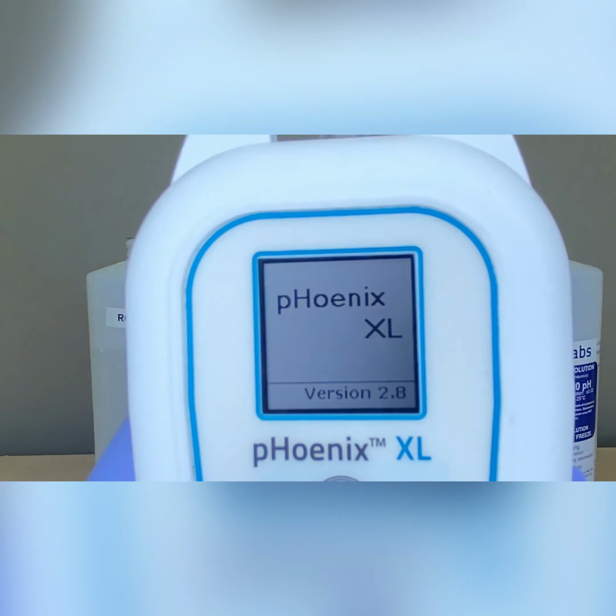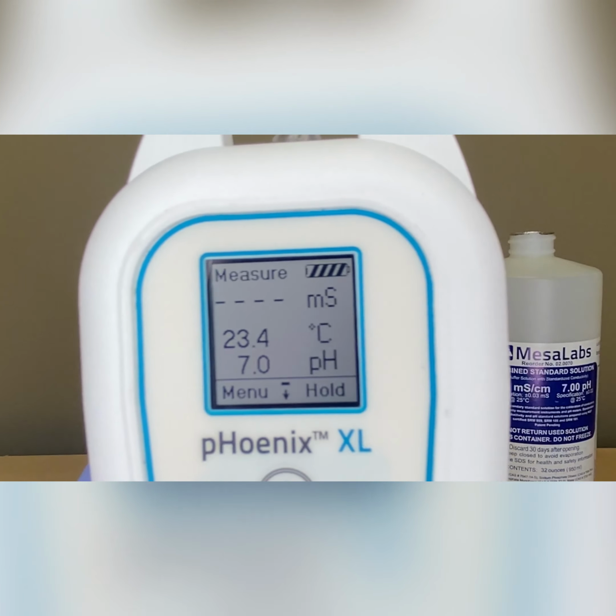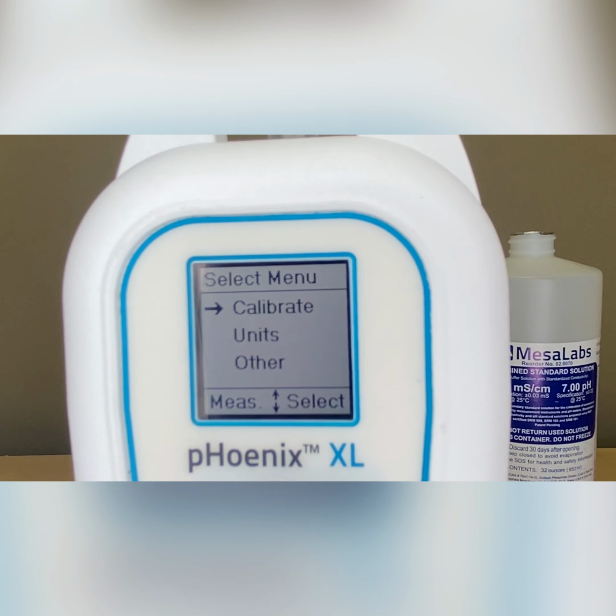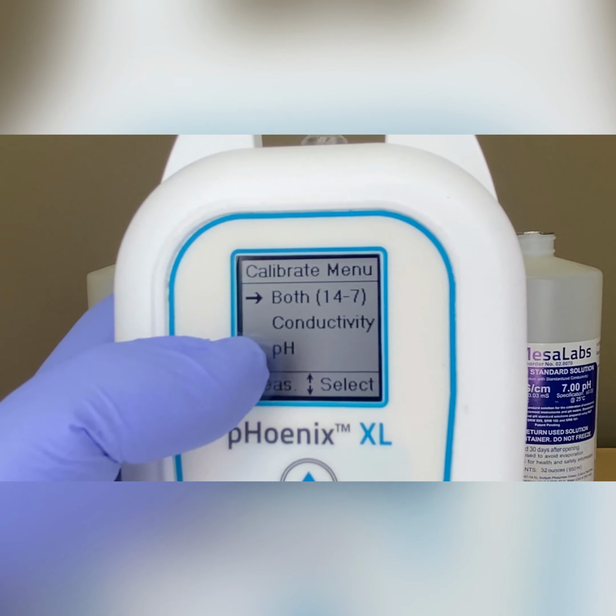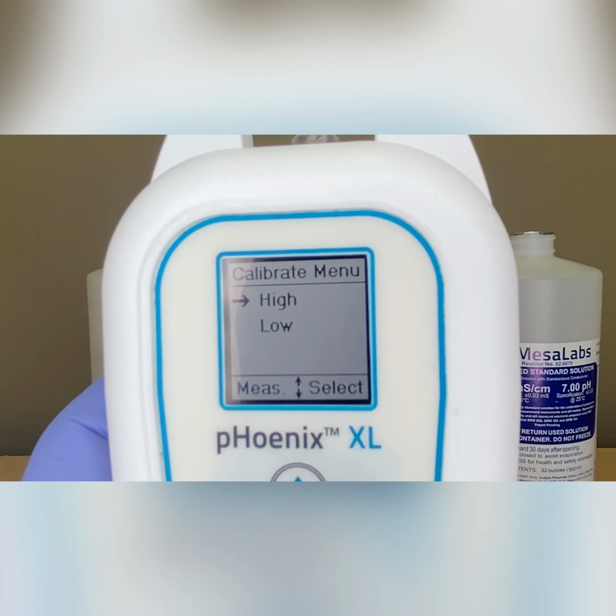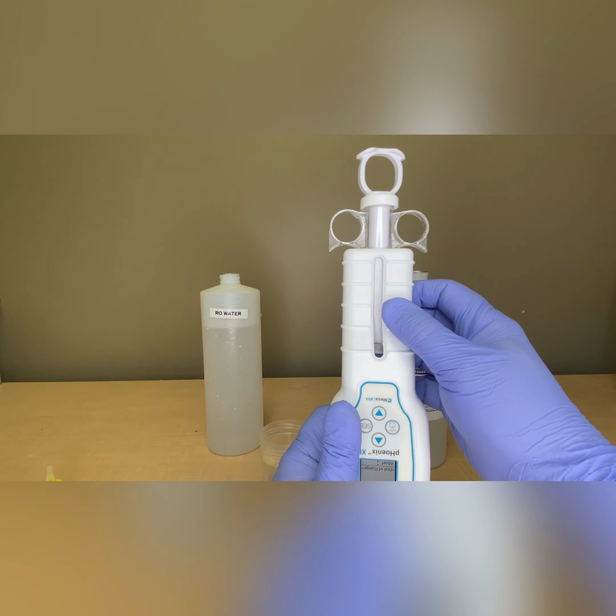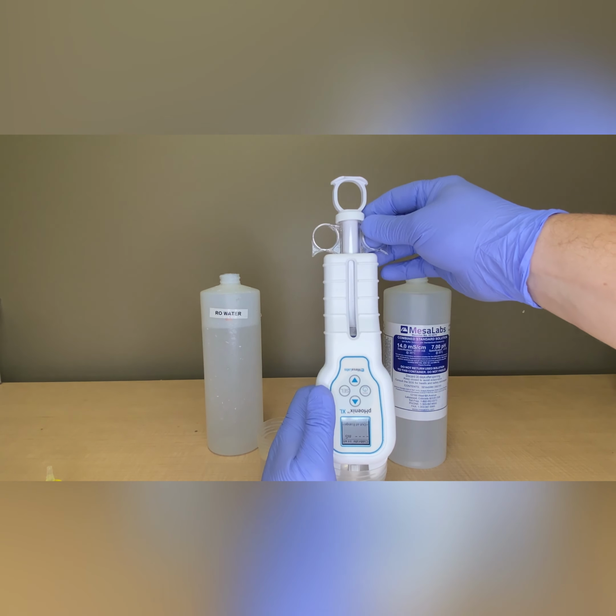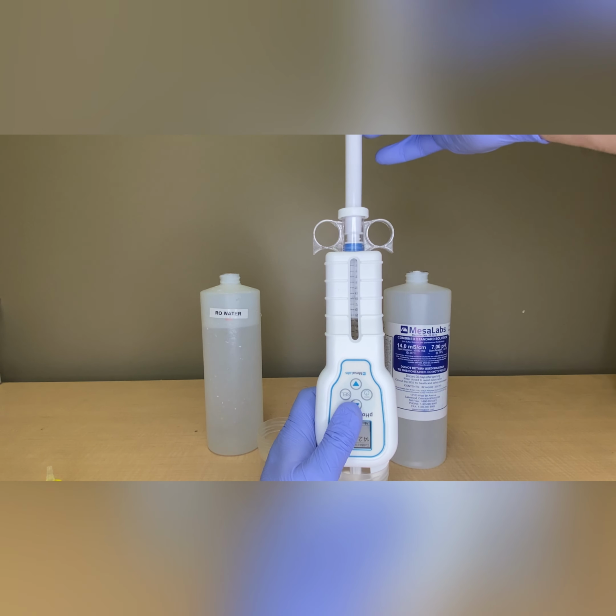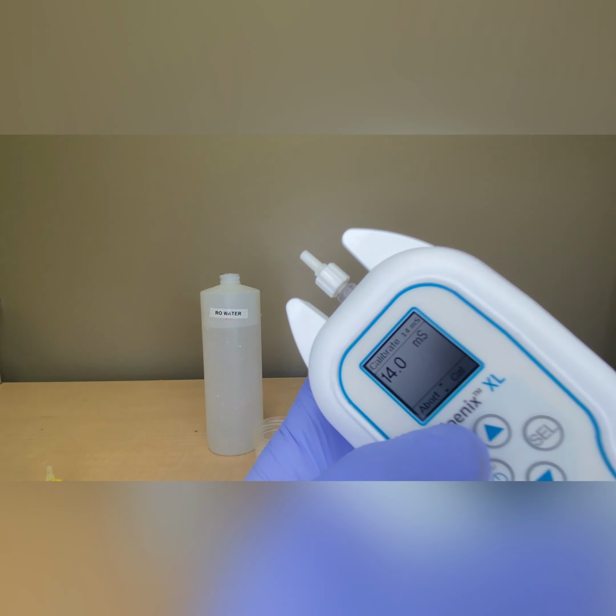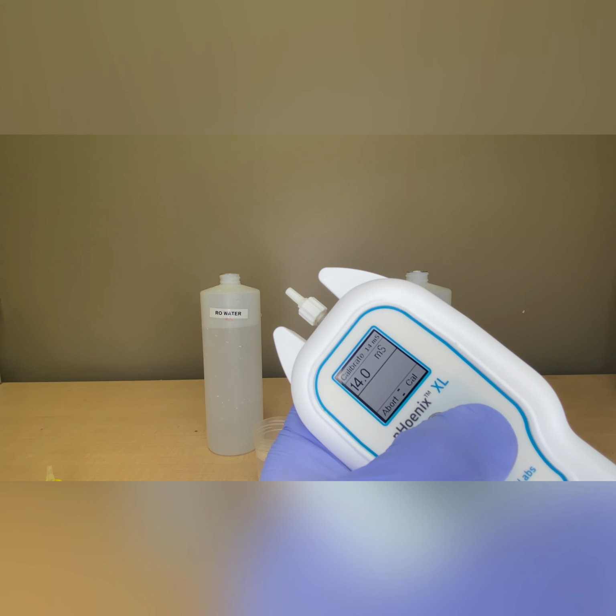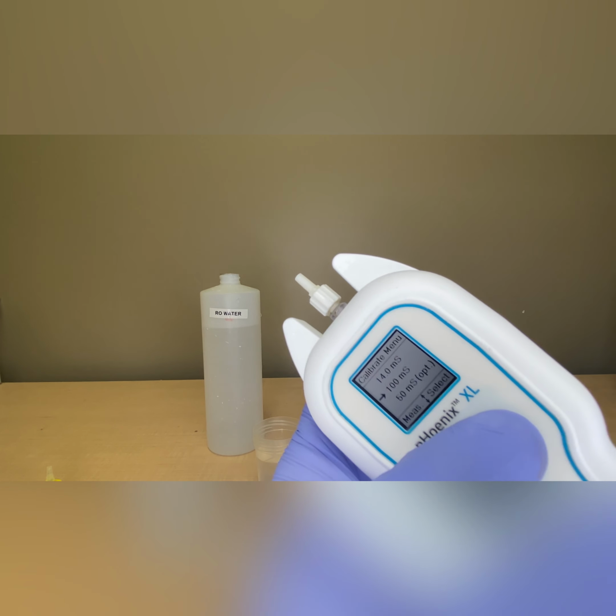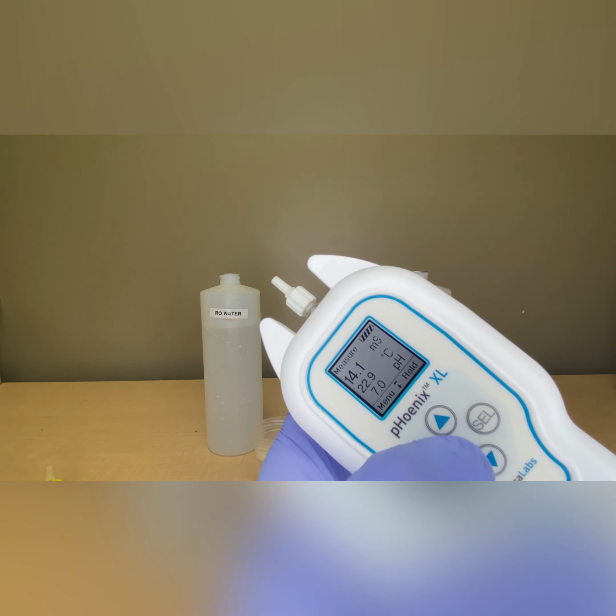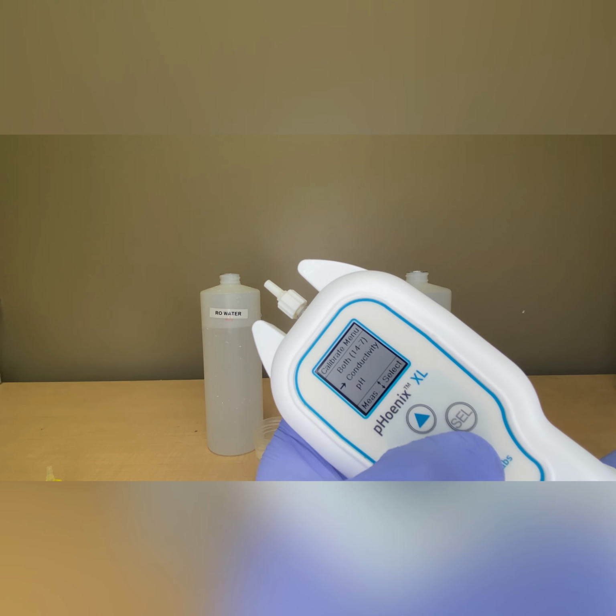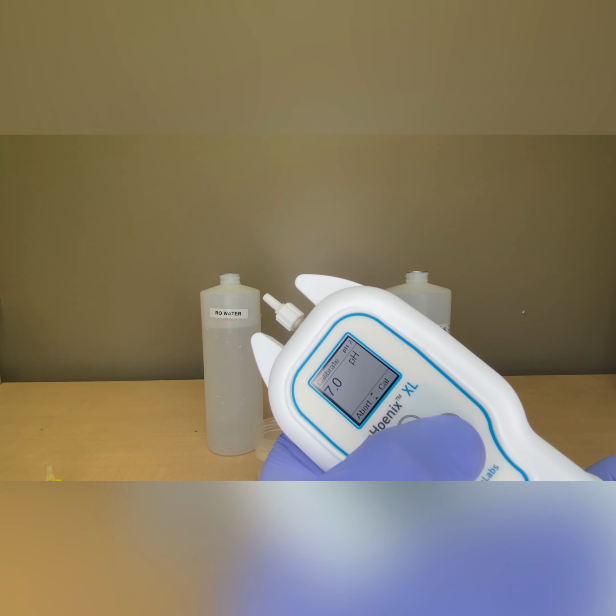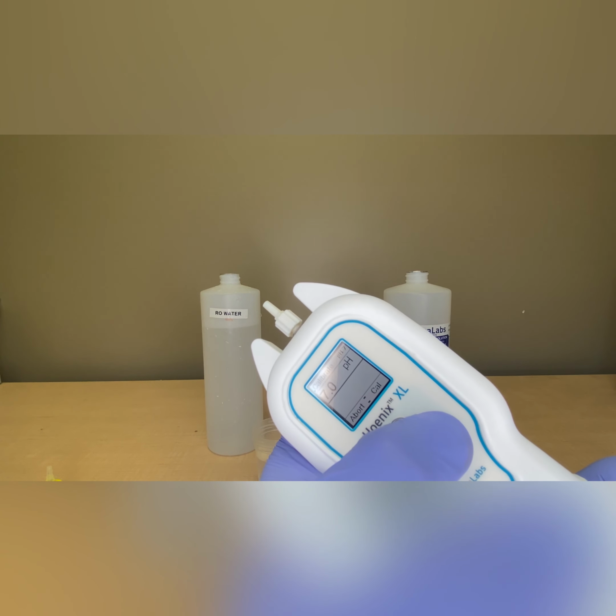And then we're going to go into our meter. I always suggest that if you're having issues trying to calibrate your meter, to use the calibrating separately method. So we're going to do that, go down to conductivity, force high, 14. And we're going to stick our meter into our cup and pull the solution through a couple of times. And we get our cal key and save. And then we're going to go back out and go into our pH calibration. And since we already have this solution in the meter, it's already there, so we'll hit cal, save that.